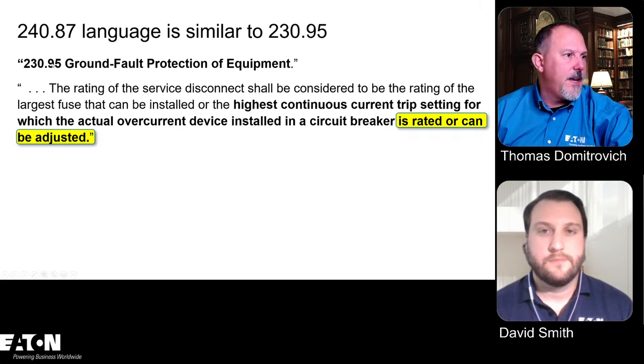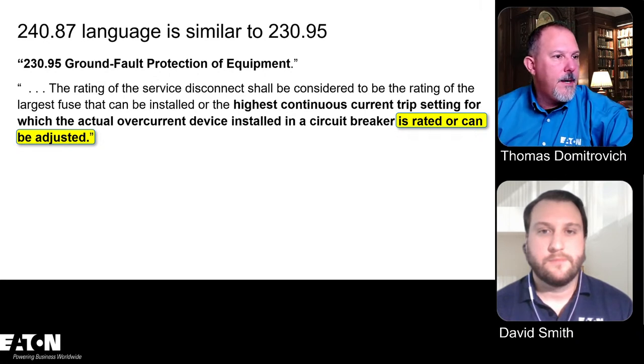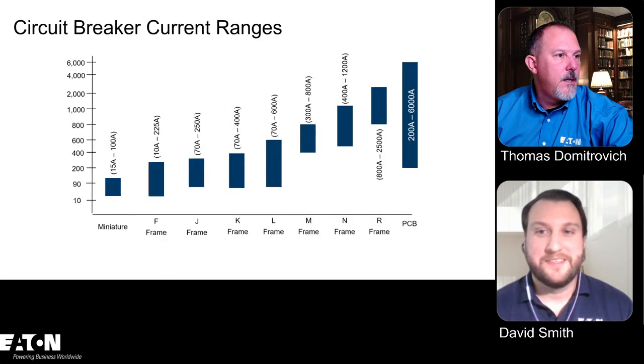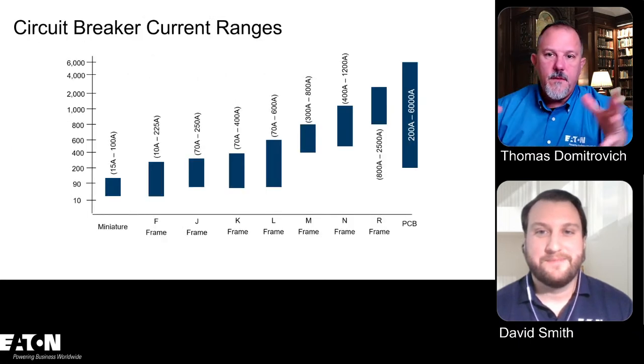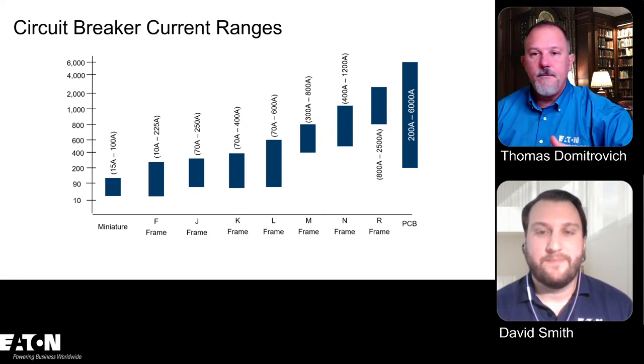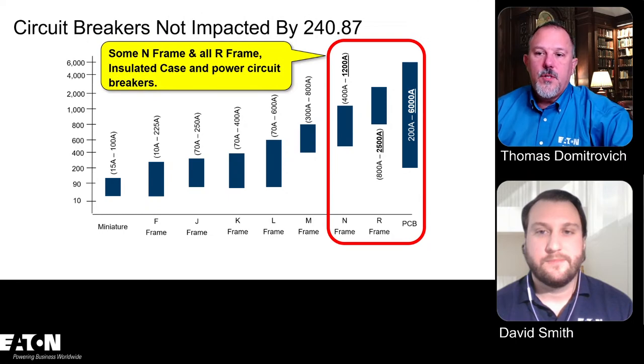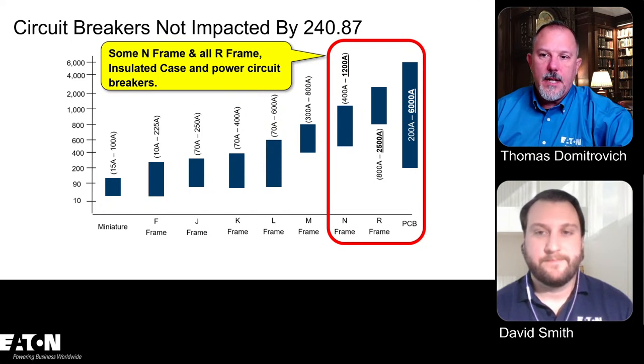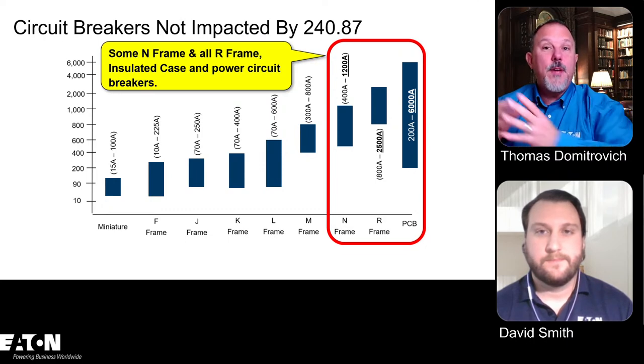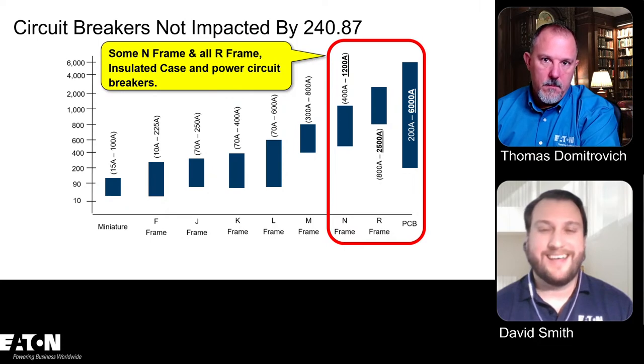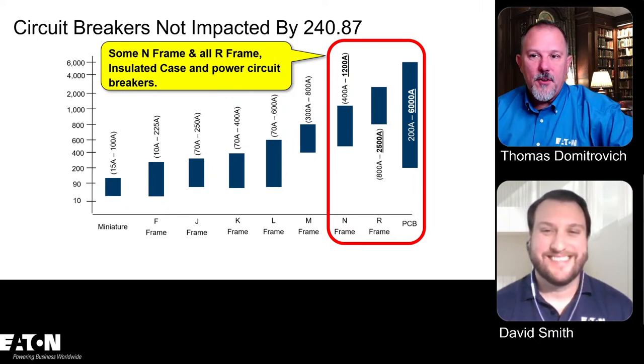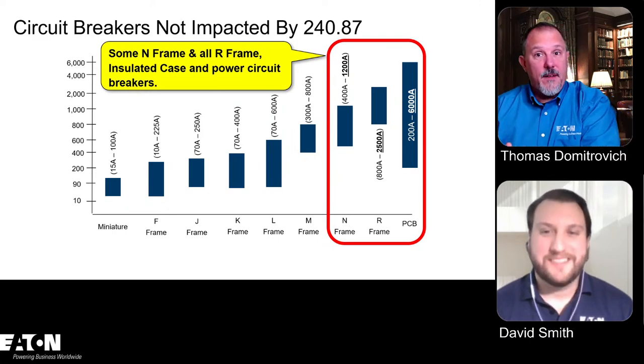And we sat down and I said, look, I'll show you those slides. In fact, here, I'll show them to you right now. I went through and said, here's all of these circuit breakers that we have. Sorry about that. And you'll notice that these are the big boys. We want to hit the stuff that goes up to like 6,000 amps. Right. And I had hit 1,000 amps, but really 1,000 amps didn't make sense because you can't buy a 1,000 amp circuit breaker. You buy a 1,200 amp breaker that can be adjusted down to 1,000 amps, but it's a 1,200 amp frame breaker.